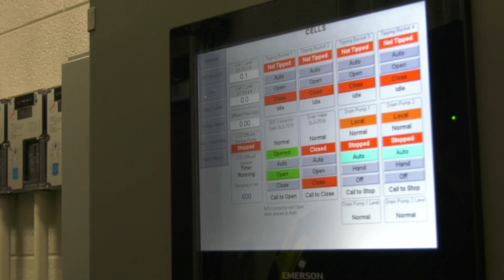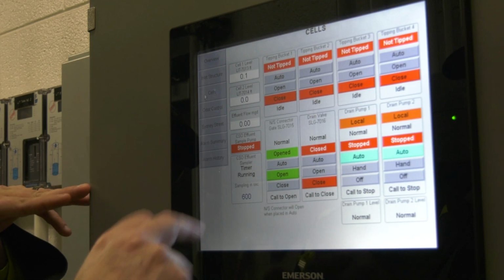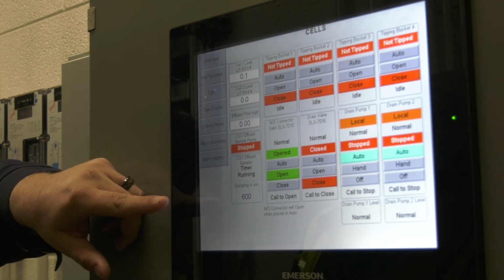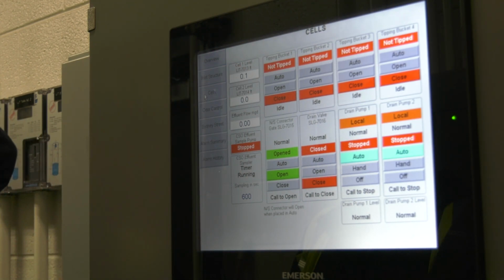Does it have some control over the sampling as well, or does it just read what the sampling is? I just saw that part there on the screen. Yeah, it reads it. Whenever your cell gets full, 10 foot, and it starts going out the effluent, then it starts counting down from 600, and it takes a sample every 10 minutes. But you don't have any control of the sampler off of this. The sampler's its standalone thing.